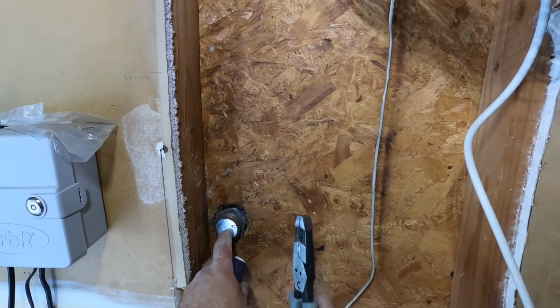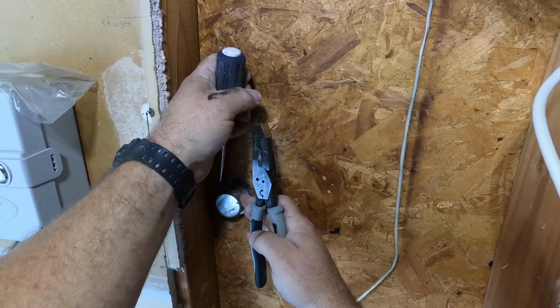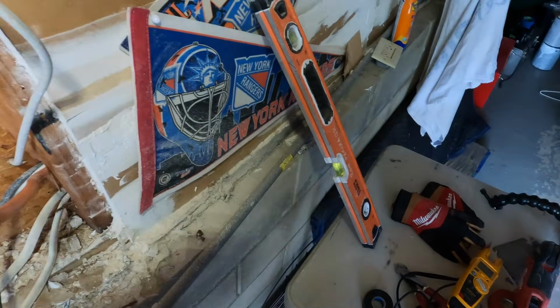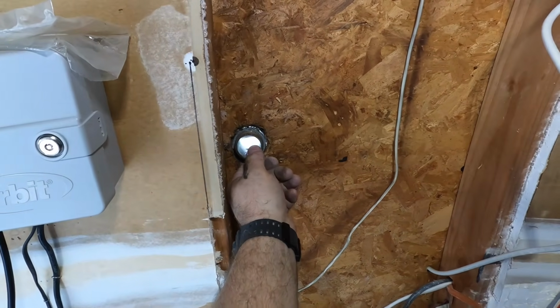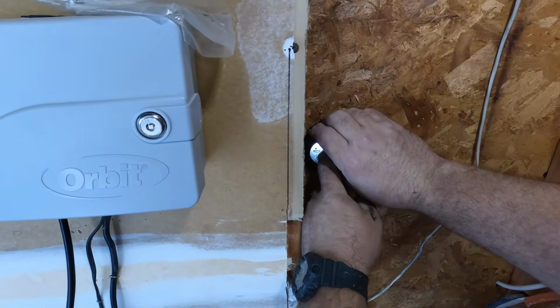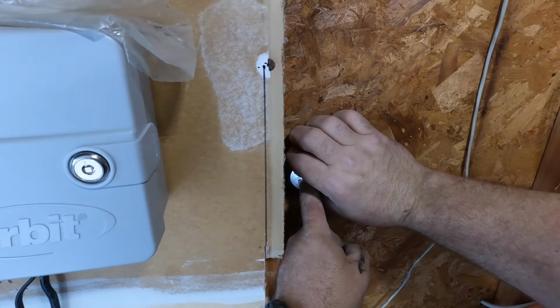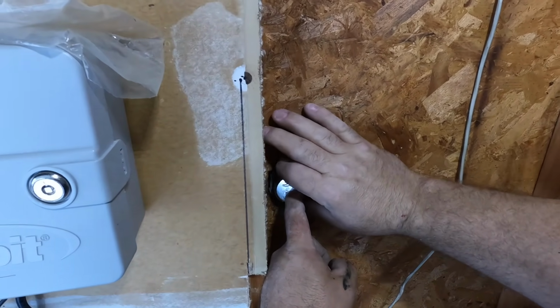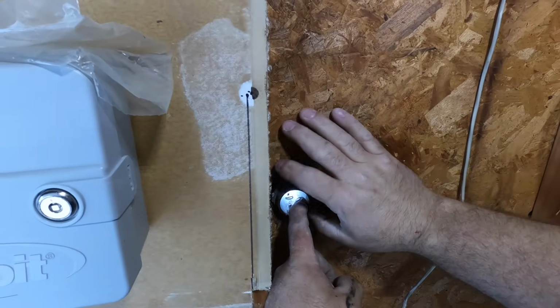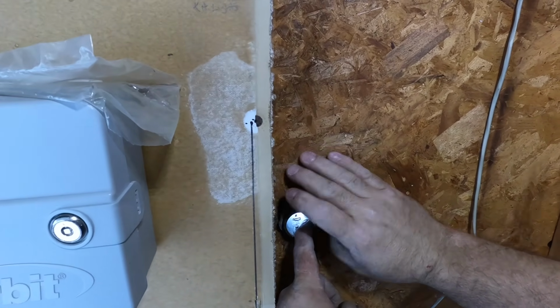So getting this nipple out, you've got to play around with it. There's a lock nut inside the panel and then on the back of the panel, and then same for the meter. So you've got to play around with this for a little while, and I've got to reuse that hole, enlarge it so I can get a 2-inch nipple in between the meter enclosure and the panel.